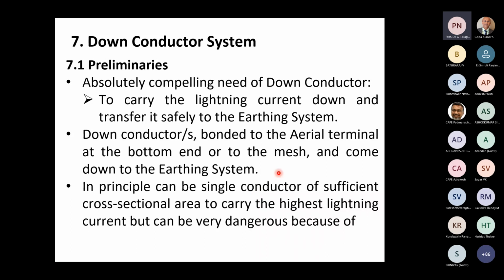Now, this will help the current to distribute all over this length of the bonding conductor, which is a very important parameter for ensuring the safety. Now, in principle, suppose you have got a 200 kiloamperes current stroke. What's the minimum area required for the conductor? Now, if you ask me, I can say that if you have got a 6 millimeter diameter copper conductor, it's enough. It will pass the current.